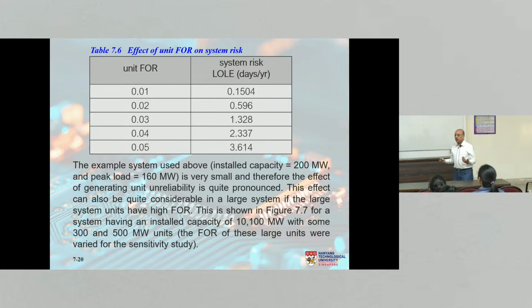Where do you want to draw the line? It's entirely up to you. If you think that it will drop to such an extent, then you need to be prepared for this risk in your system. Are you going to do anything about it by adding more generators, or reinforcing the system in other ways, or not? Maybe you want to allow the system to degrade, because there is still uncertainty. Maybe it's not going to go to 5%. Maybe it'll only go down to 2%.